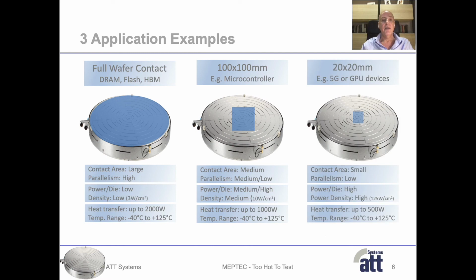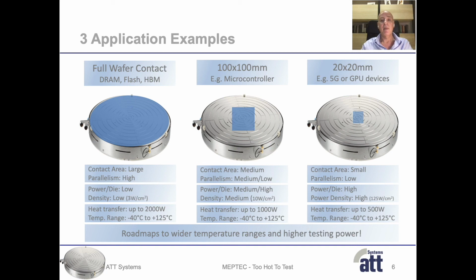Finally, we will cover small or single devices like graphics processing units or 5G devices. The contact area is very small, the parallelism is low, but the power density is quite high, with up to 125 watts per square centimeter. The applied power depends on the product and can be up to 500 watts at this point of time. The temperature range is the same as for the first 2 examples.